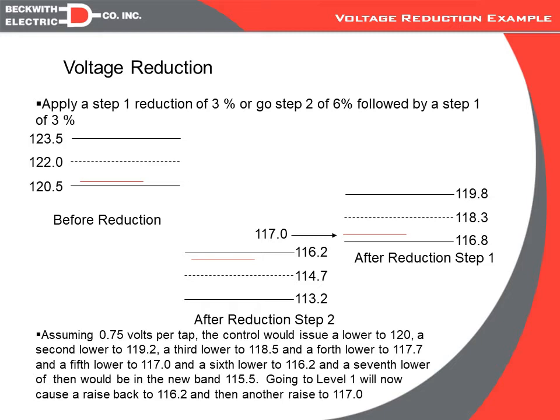So with this in mind, it's important to realize that with voltage reduction, you're never going to get what you request. And the amount you actually do get is going to be determined by the size of your bandwidth. So the larger the bandwidth, the less percentage you're going to get, because the quicker you're going to come into the new band. If I had a 2-volt bandwidth, then this would be 119.3. And where we were 119.2, we would still be in band. So in that particular case, it still would not have helped us.